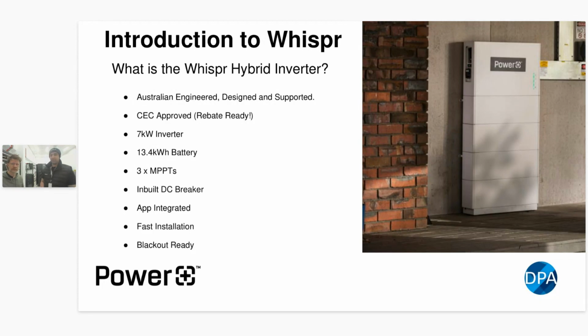We also have inbuilt AC breakers, so you'll have your AC input for the grid with a built-in breaker, same for the EPS circuit or backup circuit. That means you don't need a subboard. It's a bit of a grey area, but it may mean you don't need an ugly AC isolator right next to it, as long as you apply the correct label to the inverter. I should stress it is a grey area, we'd have to double check the ruling, because that AC isolator might be needed when you remove equipment, and in our case when you're removing equipment, the AC isolator comes with it.